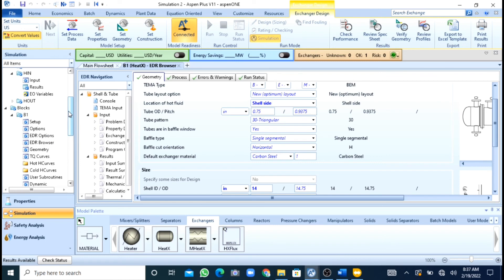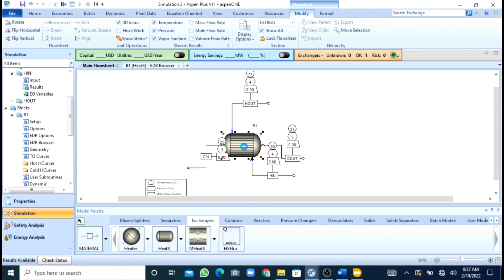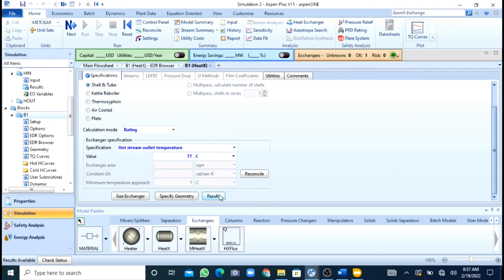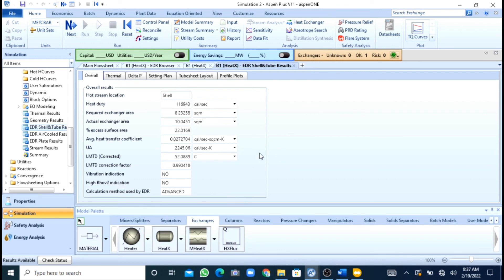Now you can see that our results are available. I will go to results. The required exchanger area was 8.23 as calculated in EDR, and the actual area is 10.04. The excess is 22%. If excess design is up to 15% it is acceptable.